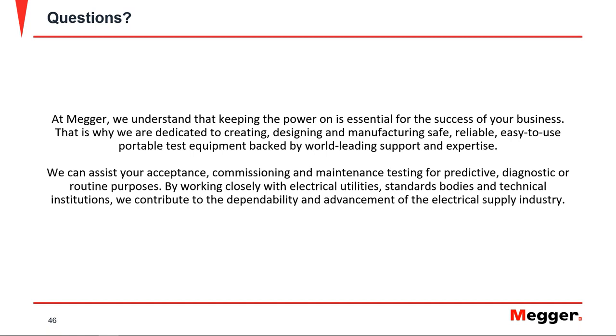Okay, certainly. As we covered, especially when you're testing the overload elements, the thermal elements of the breaker, that gives you a hint that when you are injecting the current, you're testing the thermal elements of the circuit breaker. And certainly you can do this exercise: if you test phase A in the breaker and you do a long time test, you're going to inject the current for a few seconds. And if you immediately test phase B, you might not get the same or even close tripping times for that phase.